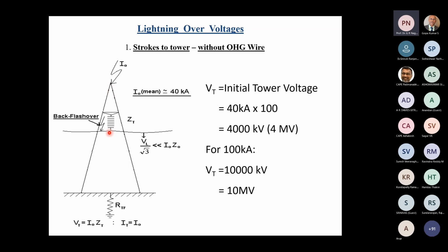the potential of the line conductor is very small. So the flashover occurs from the tower across the insulator, from the tower, that's this end, to the phase conductor. So the potential of the tower end becomes 4 megavolts here. Then that causes a potential difference of maybe 3.8 megavolts between the top of the insulator string and the phase conductor. So it causes a flashover. We call this a back flashover.